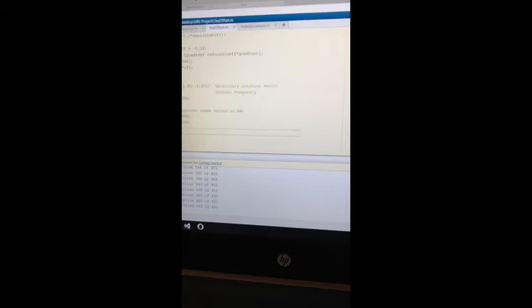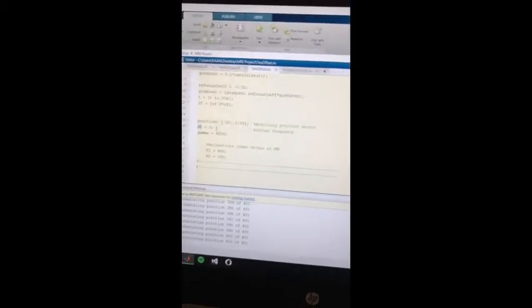I worked on the offset frequency. Now, when I add an offset frequency to the magnetization, I expect that the phase profile and magnitude profile will shift, because changing the frequency of the RF pulse, or adding an offset, is how we choose the slices in the first place. So for this, I add a variable called df. Initially, this variable is 0, so I calculate everything normally, as I showed before, without any offsets.